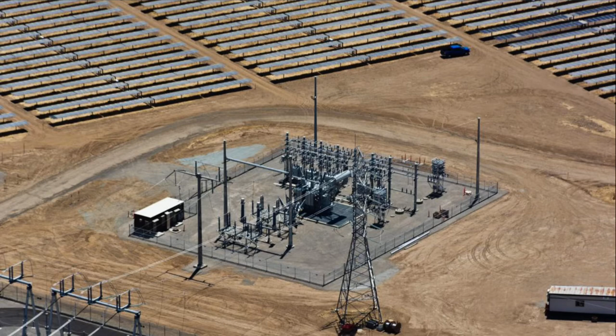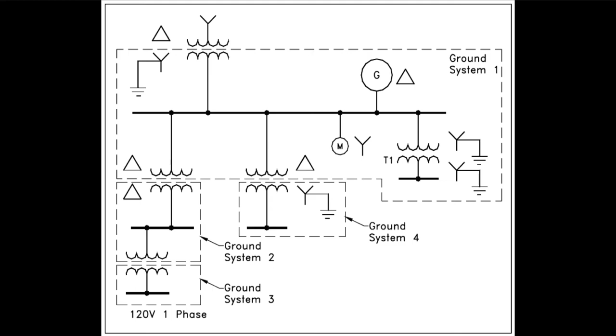And then when we get to the secondary of a low voltage transformer from 34.5 down to, let's say, 600 volts or whatever it is, then that connection is not a service grounding electrode connection. That is a separately derived system grounding connection, because now you have galvanic isolation between the 34.5 and the 600 volts. And so just like inside of a building where you go from 480 to 208, the 208 side gets separately derived and separately grounded. But you still call it a grounding electrode conductor? We'll still call it a grounding electrode conductor, but it will not be connected to the main service grounding electrode conductor other than through building steel and things like that.